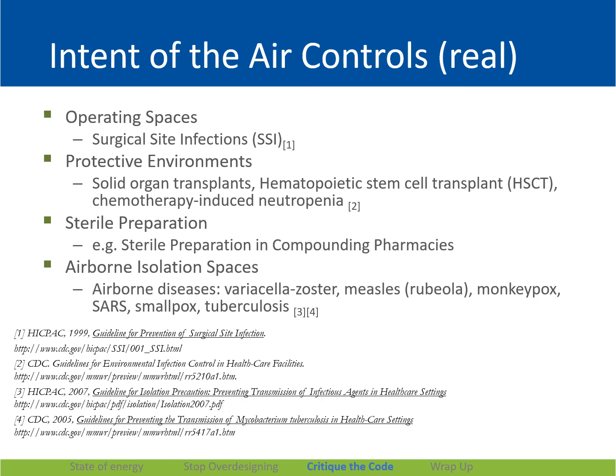I have been critical publicly of ASHRAE Standard 170, the air change table. It is an outdated paradigm, and most of the numbers in it are not credible. Before I go too crazy on critique, let me say there are areas in hospitals where HVAC systems need to do some pretty clear things. We have a few clean spaces and some airborne containment. The clean spaces are operating rooms where we want clean air to mitigate surgical site infections, protective environments for severely immune compromised patients, and then we also have pharmaceutical compounding where we're mixing up pharmaceuticals.